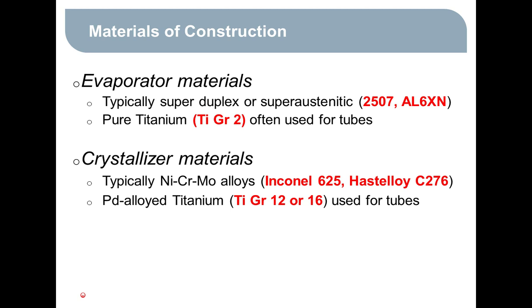Well, typically on the evaporator, we're looking at a minimum of a super duplex 2507 type stainless steel or a super austenitic stainless steel like AL6XN or 254 SMO. Tubes are generally titanium, pure titanium, for their corrosion resistance because the tubes are the thinnest part of the evaporator. So grade 2 pure titanium is often used for the tubes.